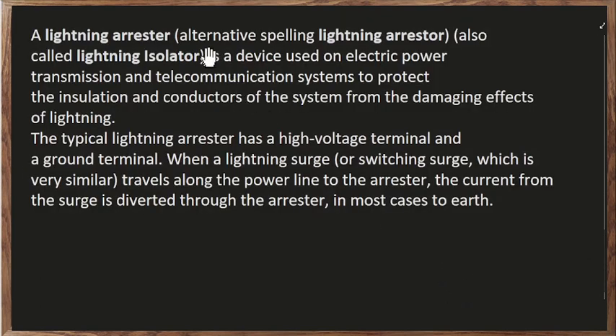Then we have the lightning arrestor, also known as lightning isolator. It is a device on the electric power transmission and telecommunication system to protect the insulation and the conductors of the system from damaging effects of lightning. A typical lightning arrestor has a high voltage terminal and a ground terminal. Tapos, they are connected using the down conductors, or the conductor from the high voltage terminal to the grounding. So when a lightning surge or switching surge, which is very similar, travels along the power line to the arrestor, the current from the surge is diverted through the arrestor in most cases to earth.